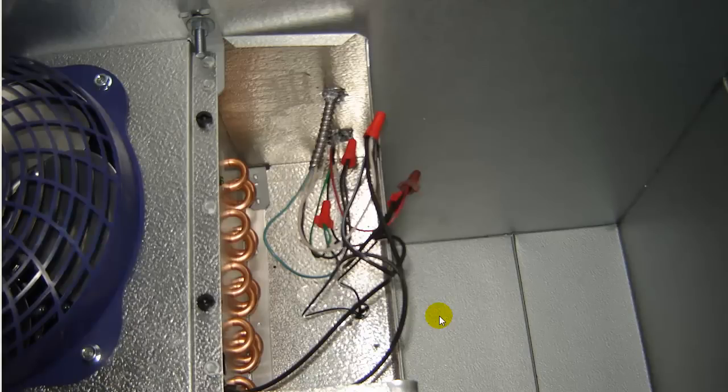Today I want to show you this walk-in cooler that I walked up to the other day and noticed MCs hanging down out of the ceiling. They just punctured right through the roof of the walk-in cooler and kind of stuck them in there and sealed them up with gray silicone caulk.